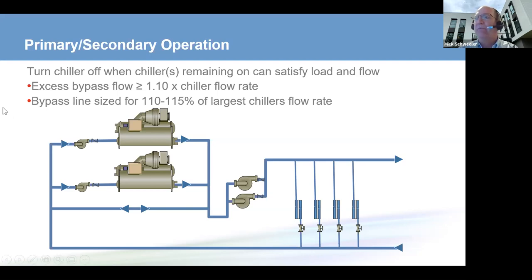When we have a primary secondary system, we have 2-way valves on the coils, variable speed drives on the distribution pumps, constant flow through the chiller evaporators, and then a bypass line with no valves and no devices that makes up the difference between the variable flow that's going out to our loads and the constant flow going through the chillers. The way we can determine whether or not we can disable a chiller, that is to turn one off, is when we have enough excess flow in this bypass line.